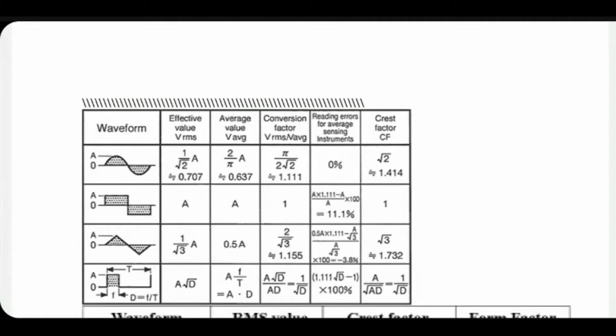VRMS upon V average is an interesting parameter to know. It is known as conversion factor. You can calculate this. It will turn out to be approximately 1.111 for this particular case. Okay. Reading errors. We'll come to measuring part later. Okay. Don't look at this column right now. Crest factor is peak value divided by RMS value. So obviously, this is square root of 2, which is 1.414 approximately.